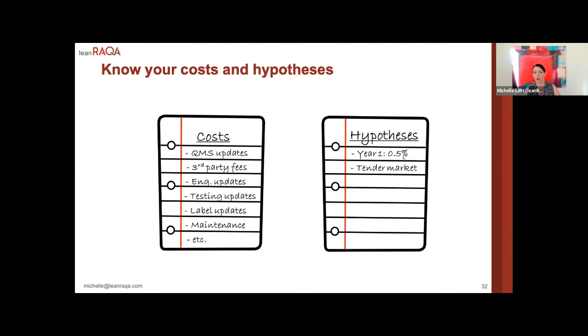You're going to have third-party fees, as we saw in the complicated picture. You're going to have a European authorized representative, a Swiss authorized representative, a UK authorized representative. You're going to have a notified body. And your notified body is going to have to audit you for your quality system certification and audit your critical suppliers. So these costs can get quite pricey in just external fees.